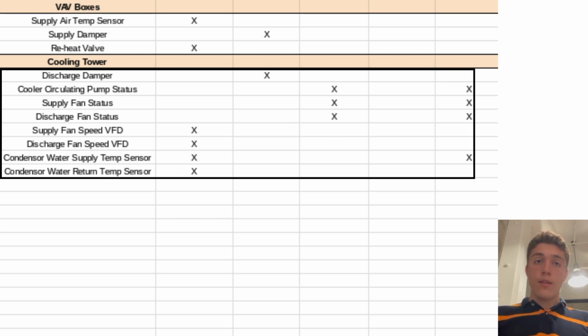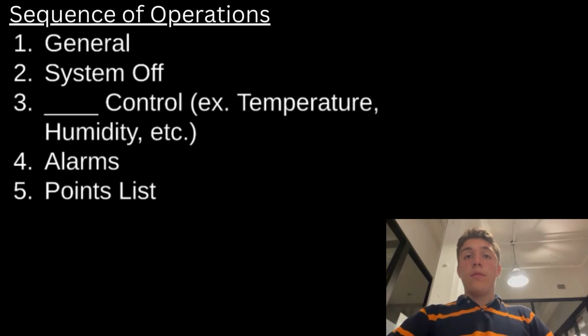We have a couple of alarms linked to these, such as the statuses and the supply temperature sensors, just to make sure that they're not too high, or else that could damage the equipment. And that just about covers all the points that I'm going to be using. So I have the points list, which is a good part for my proposal. In the meantime, I'm going to start teaching myself about diagrams, but this is also a sequence of operations, which is a very important part of the proposal process.